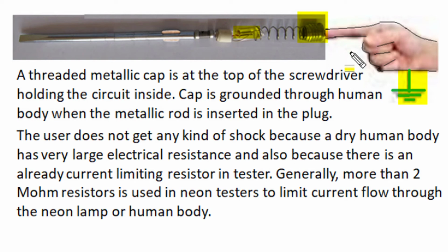But to limit current flow in this circuit, we also use a high value resistance in series of this circuit, and typically this resistance has a value around 2 mega ohm, so that when we use this circuitry on a 230 volt supply, the current flow will be limited to the 1 milliampere range or remain even less than 1 milliampere. Now 1 or 2 milliampere current is let go current, which when passed through the human body won't make any difficult sensation, as our body can bear the flow of a small let go current of the order of 1 milliampere or less.